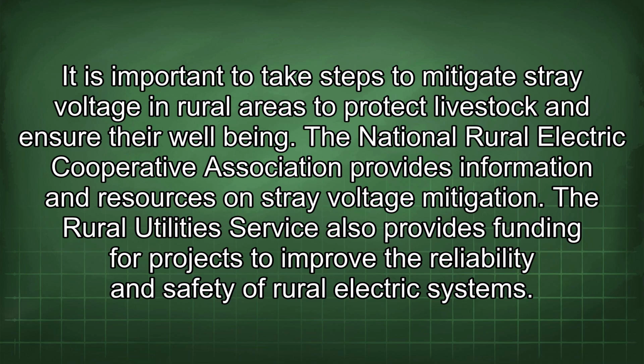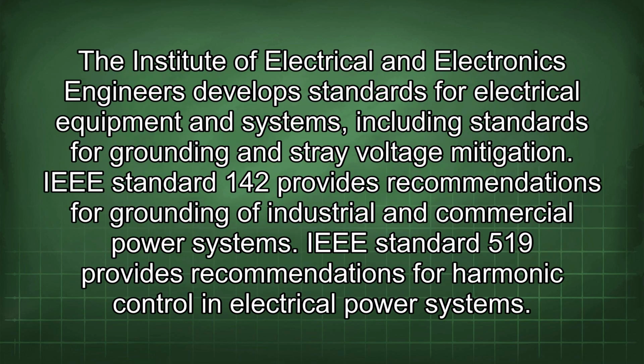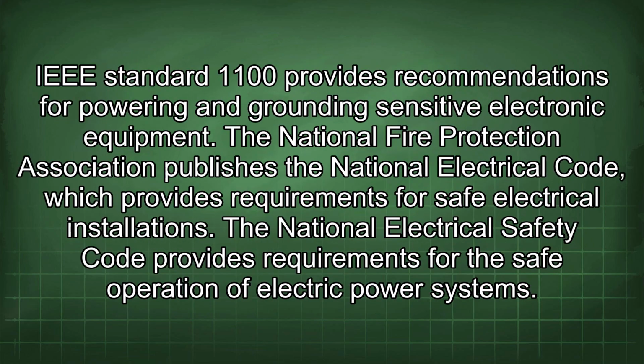The Rural Utility Service also provides funding for projects to improve the reliability and safety of rural electric systems. The Institute of Electrical and Electronics Engineers develops standards for electrical equipment and systems, including standards for grounding and stray voltage mitigation. IEEE Standard 142 provides recommendations for grounding of industrial and commercial power systems. IEEE Standard 519 provides recommendations for harmonic control in electrical power systems. IEEE Standard 1100 provides recommendations for powering and grounding sensitive electronic equipment.